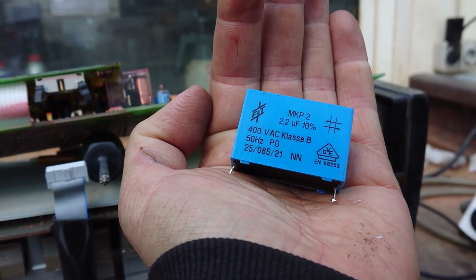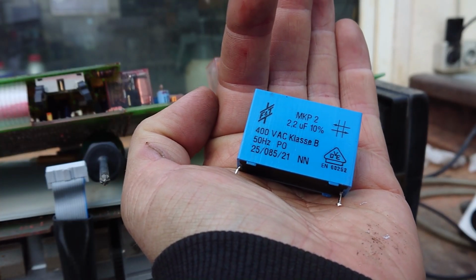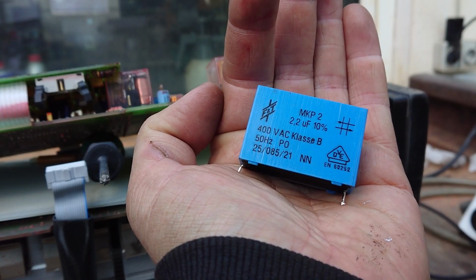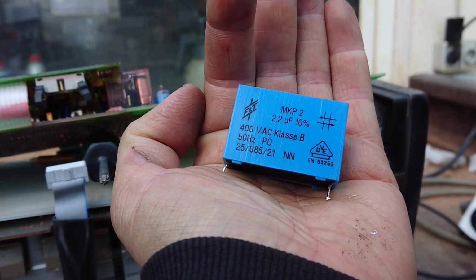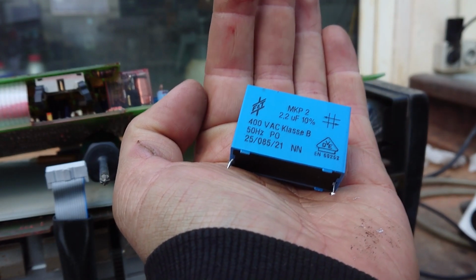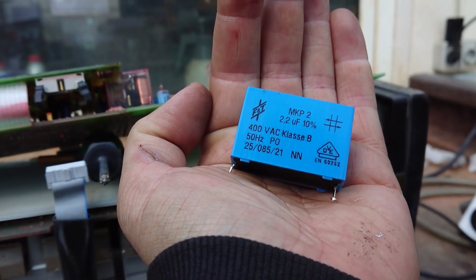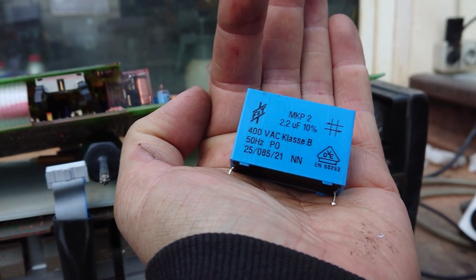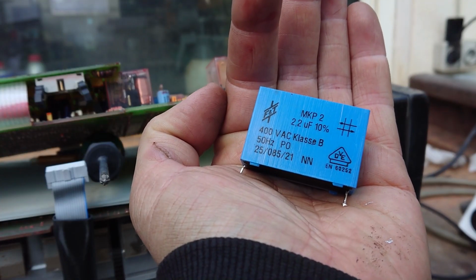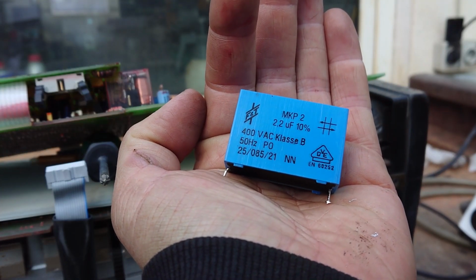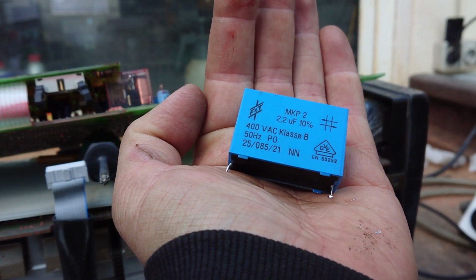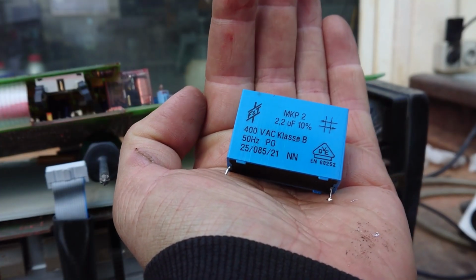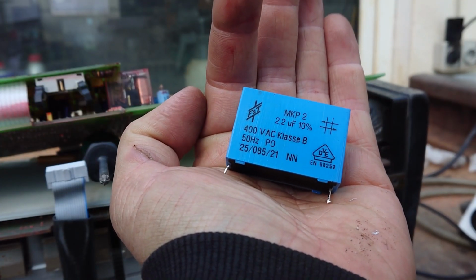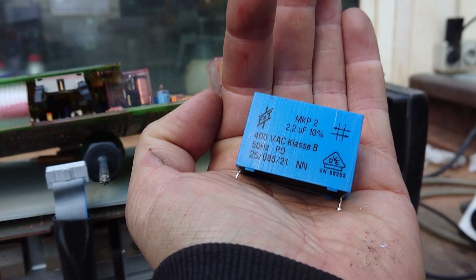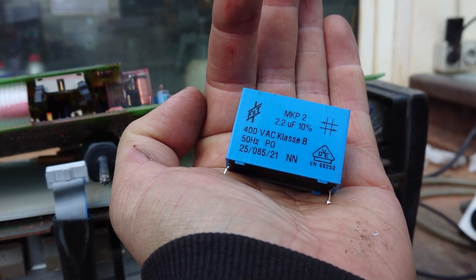MKP is the capacitor technology that is used here. It's a metallized polypropylene capacitor. It's abbreviated MKP because it's based on German terminology though. Especially in this application, you will often find Class X capacitors marked MKP X2 or similar. They are specifically designed to be connected between line and neutral in these filter circuits and are not to be confused with Class Y capacitors.